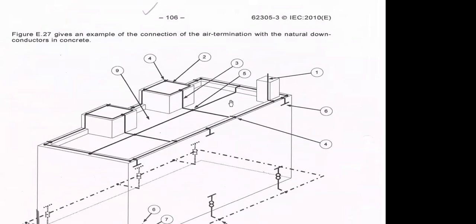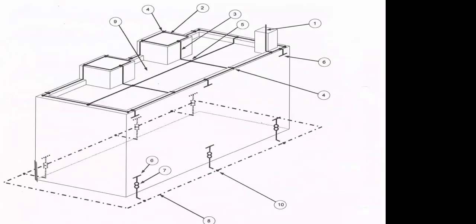As I discussed, this is a pictorial representation of using the building structure as earthing. What you see here is a dotted line, and again the air terminal is at the top, and the dotted lines show the earthing, where the reinforcement of the building is being used. So these also can be used, but again, we have to be doubly sure that this particular part of the building which we are using is protected, and that during lightning nobody touches these portions by mistake.